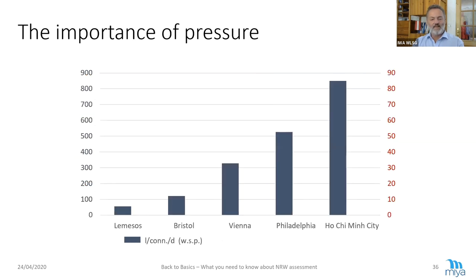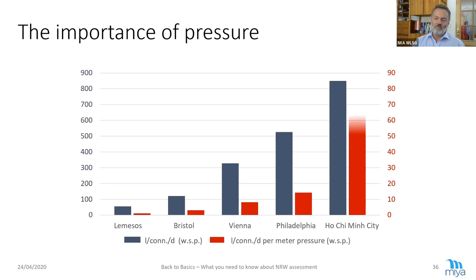Philadelphia and Ho Chi Minh City — there is not much difference when looking at liters per connection per day. The problem is we still haven't taken pressure into account. Now, liters per connection per day per meter pressure — we simply divide these values by the average pressure — and only now we get the full picture. Ho Chi Minh City is of course a much leakier system than Philadelphia.